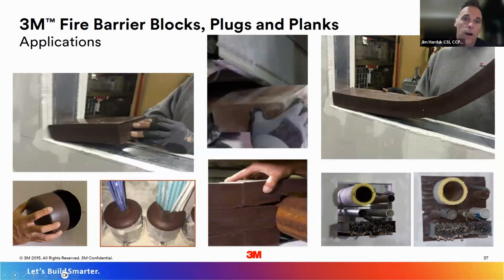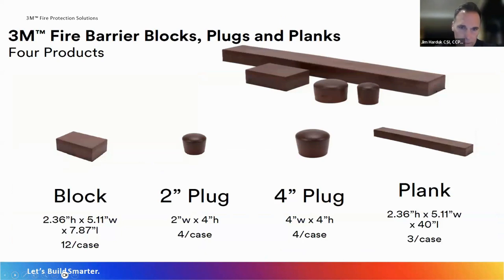So the next product here is our fire barrier blocks, plugs, and planks. So what we've done here, we've taken that 2-component urethane foam and we've basically pre-manufactured it into various shapes. So if you have a situation where maybe you don't feel comfortable using the dispensing tool in the field and using the FIP foam, you can buy these materials already prefabricated. The nice thing about the fire barrier blocks and plugs, it's a pretty economical way to close down a large opening. They're reusable and you can penetrate these pretty easily. So if you had a situation where you're using a plug and you had some cable going through it and you want to run some more cable, you could simply take an insulation knife and slit it, pull your cable through there, and then you can seal it with the FIP foam or one of our other approved fire stop sealants. Next slide. They're available in a couple different sizes and shapes, as you can see there.